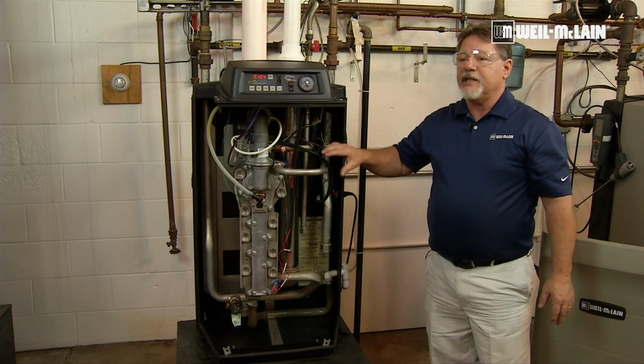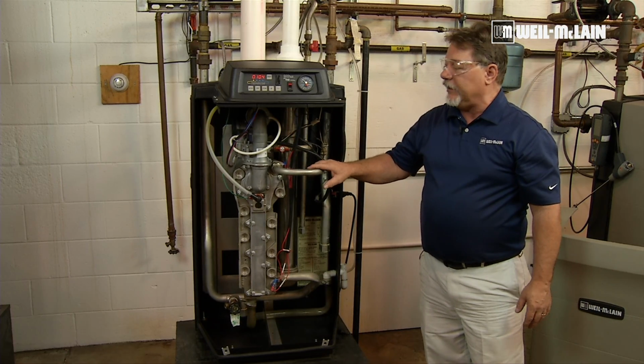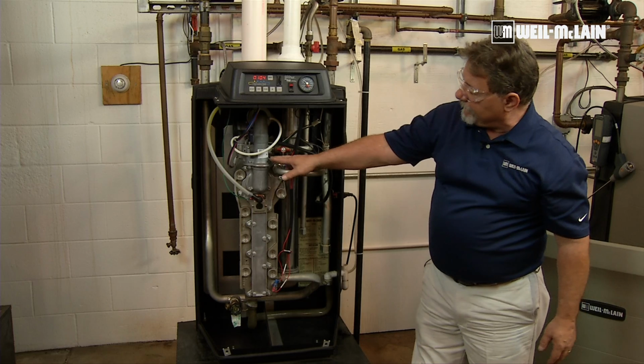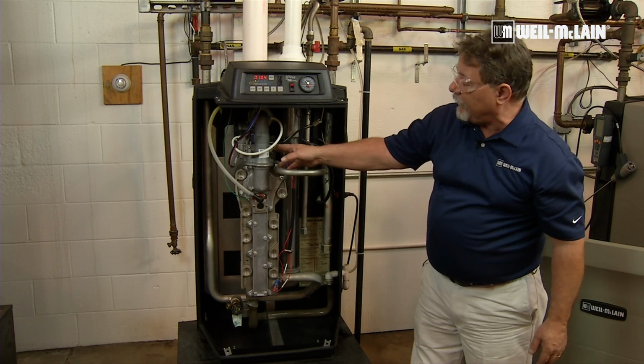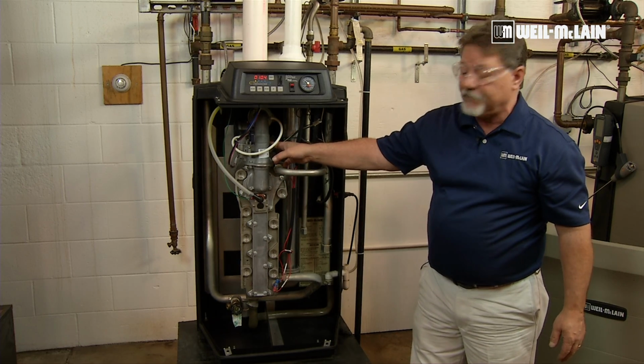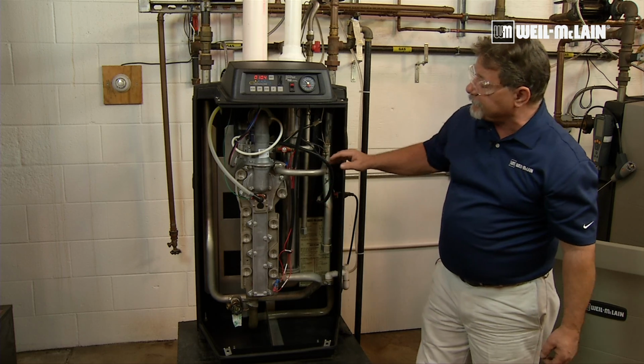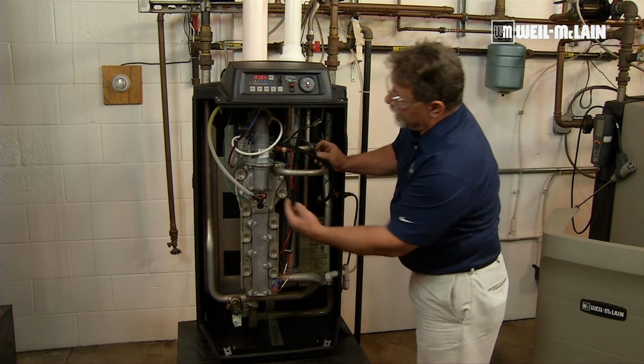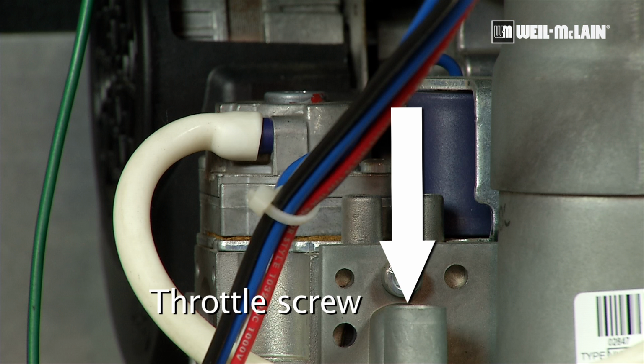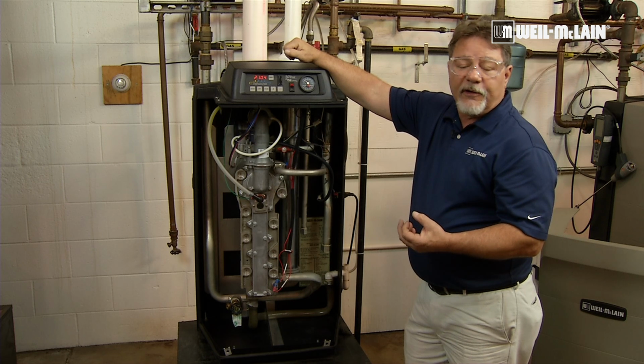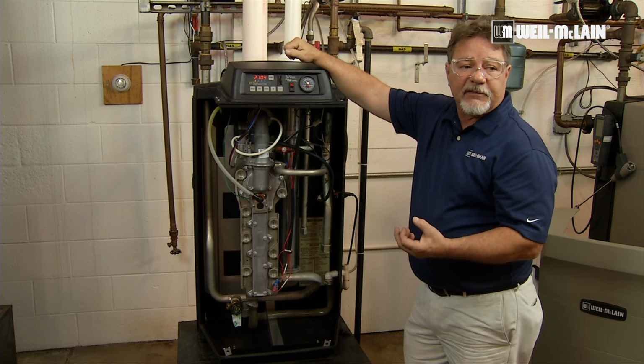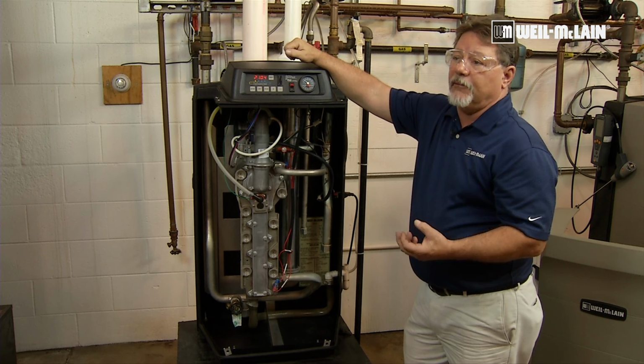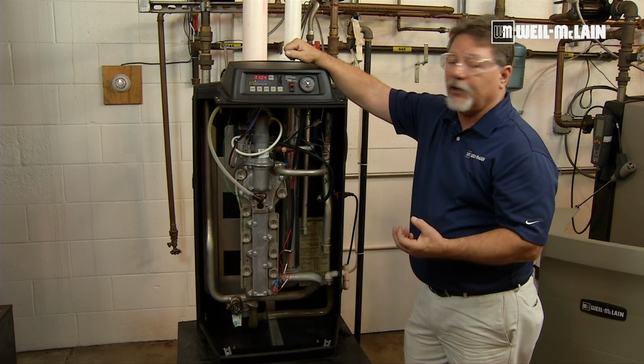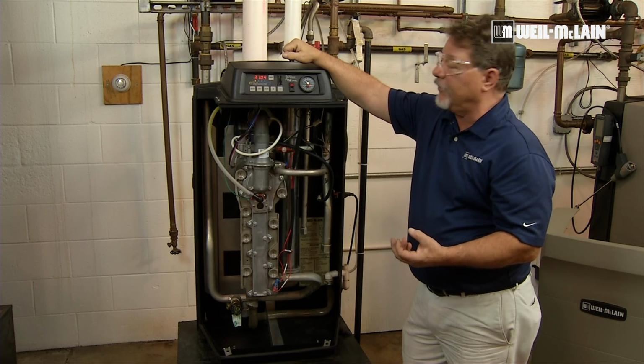So in this configuration on the 105 and the Model 80s, the gas valve Venturi and blower, the heat engine if you will, is on top of the heat exchanger. It's not down on the side. I'm going to point out back here, this is the throttle adjusting screw. Drive the boiler into high fire, set our combustions at high fire, and as well, we need to take the boiler down to low fire and take a look at the boiler there.